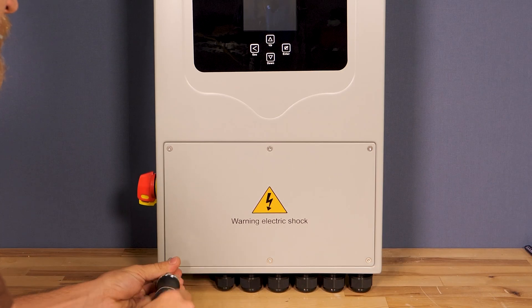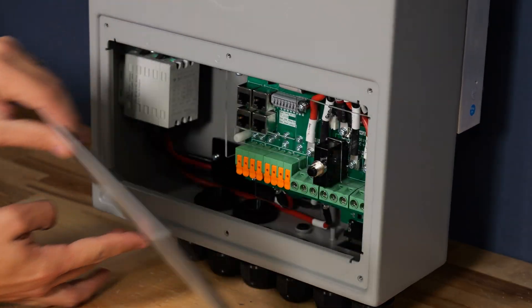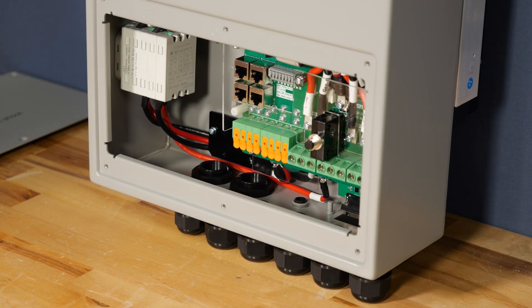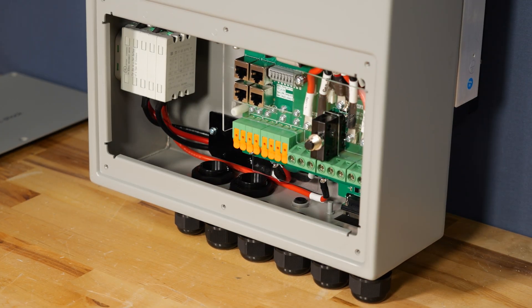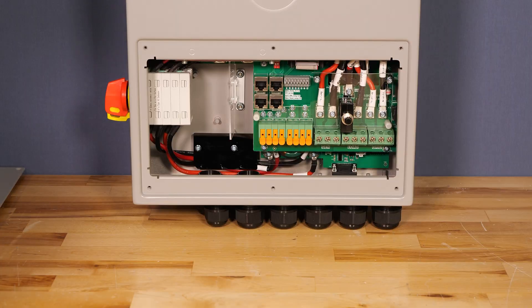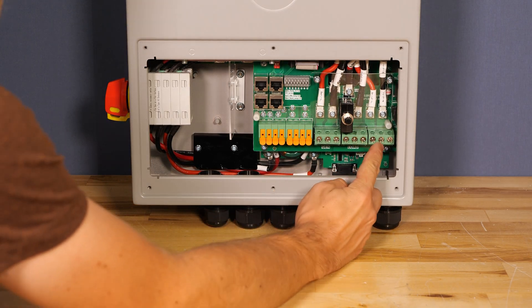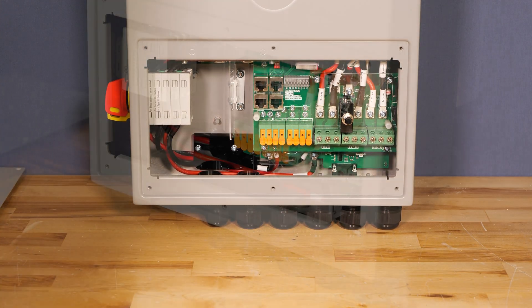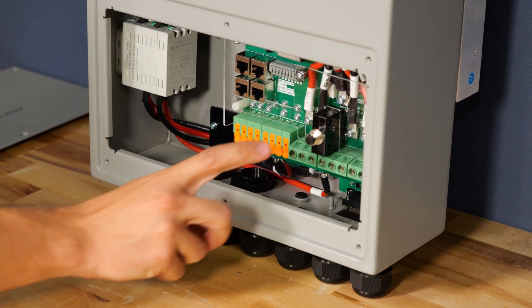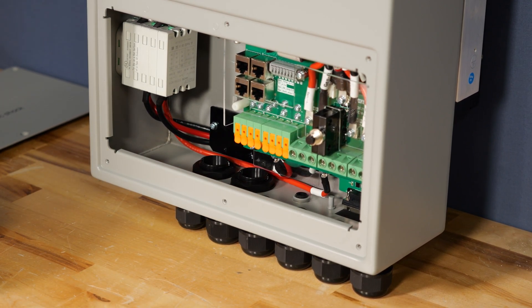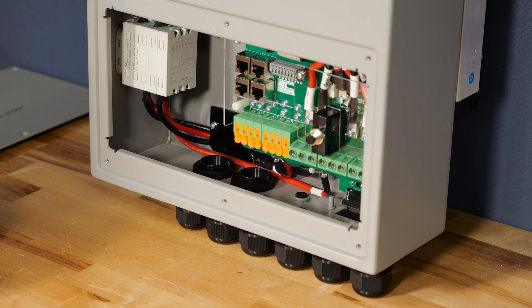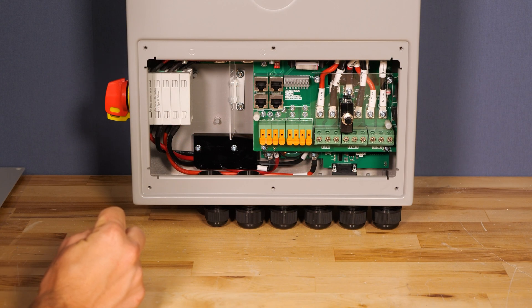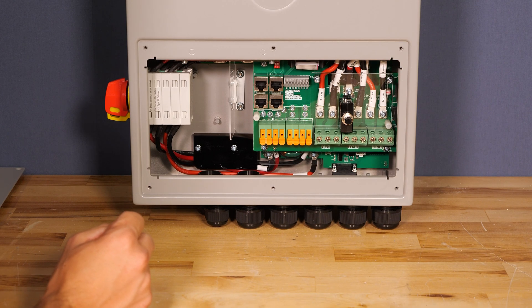There are six screws that hold on the bottom wiring compartment. If you're familiar with other Solark inverters, you'll notice this one is a little bit different. We do have our familiar grid, load, and generator terminals. However, unlike the other inverters, we only have one circuit breaker for the output and that is only an overcurrent protection device. It's not like the other inverters that have an actual disconnecting means so you can shut off the input and output power.